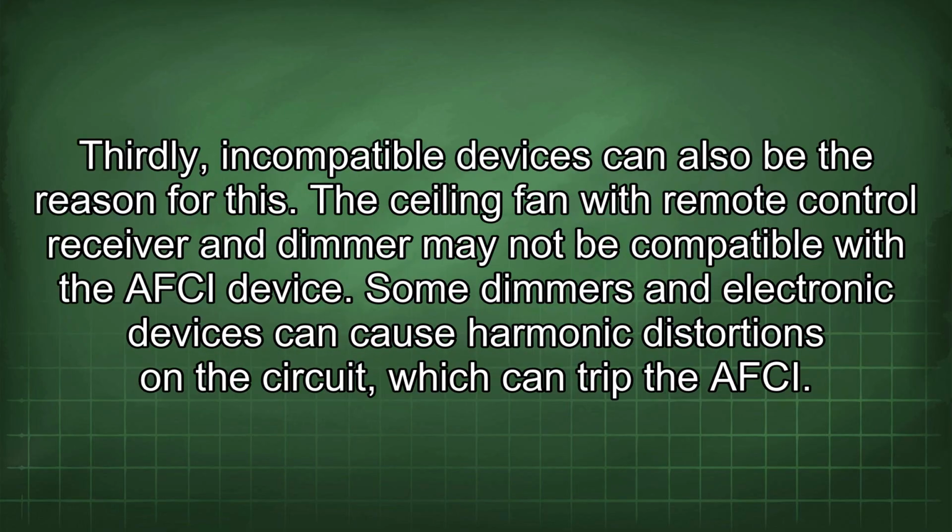Thirdly, incompatible devices can also be the reason for this. The ceiling fan with remote control receiver and dimmer may not be compatible with the AFCI device. Some dimmers and electronic devices can cause harmonic distortions on the circuit, which can trip the AFCI.